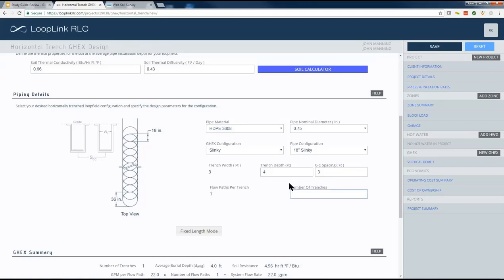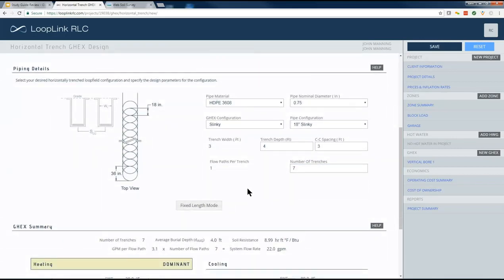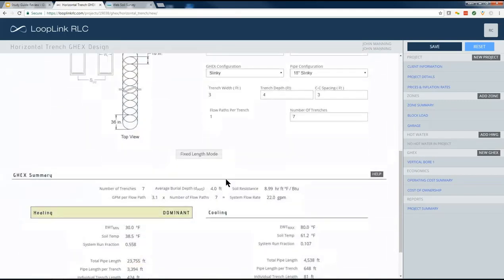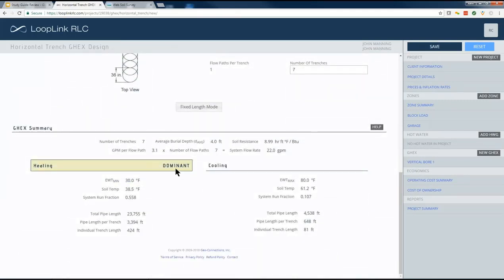So instead of individual trenches, a system like this would most likely be installed in a pit. This is a 7-ton system, so let's go with 7 trenches total. Now, if you come down here, you can see we're at a 1 loop per ton design, roughly, so you can see 3 GPM per flow path. You'll see the amount of pipe that we have to install in this specific configuration to satisfy our heating requirements: 24,000 feet of pipe, 3,400 feet of pipe per slinky loop, 424-foot trenches.